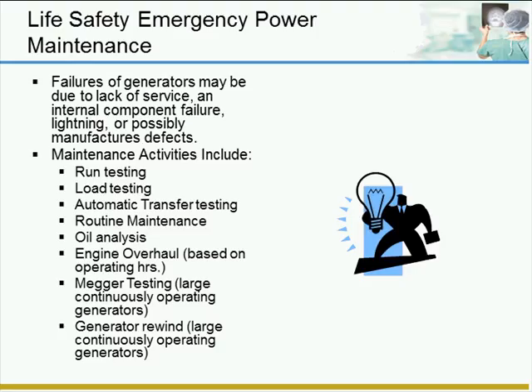Some of the larger units, you might want to do megger testing. And if you have an older unit, sometimes it's good to do a generator rewind if your megger test comes up faulty. Due to the units not being in operation that often, proper maintenance is critical. Failures of the generators may be due to lack of maintenance, internal component failure, or possible manufacturer defects.